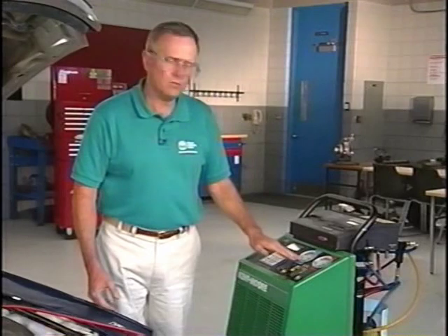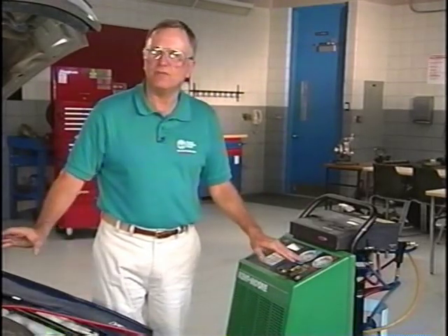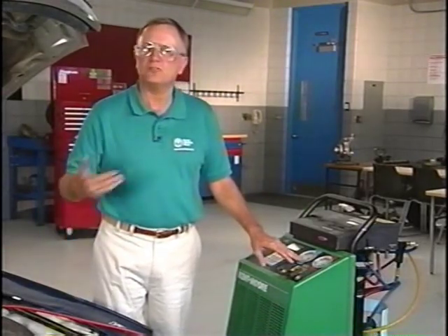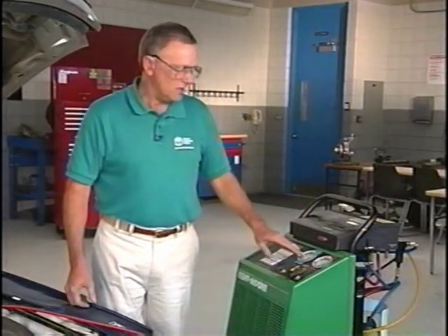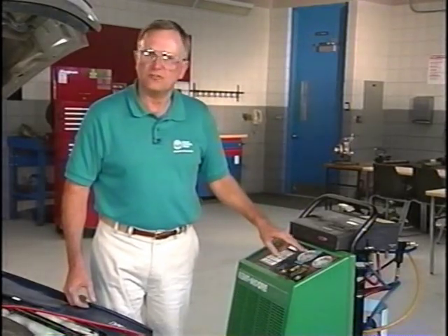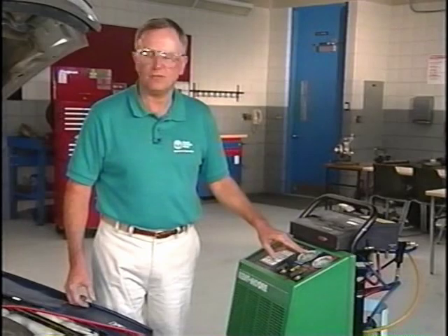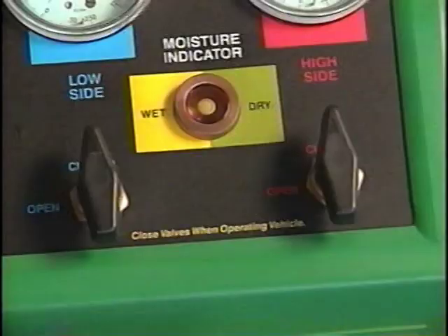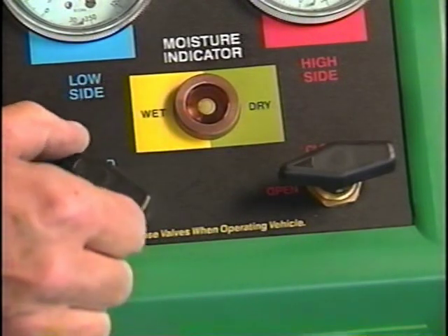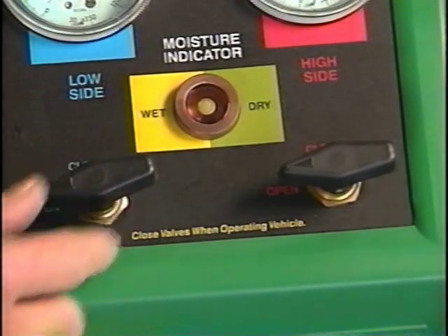If it shows 0, that indicates that there is no refrigerant in the system and recovery process isn't really required. As it shows on this gauge, it does show that there's a charge in the system, so we are going to have to recover the refrigerant. The next step then is to open the high side gauge on the control panel and the low side gauge on the control panel so we can begin our recovery.